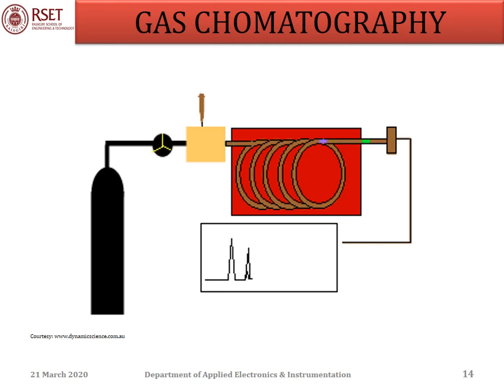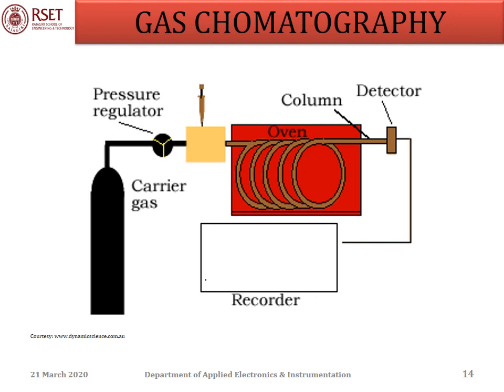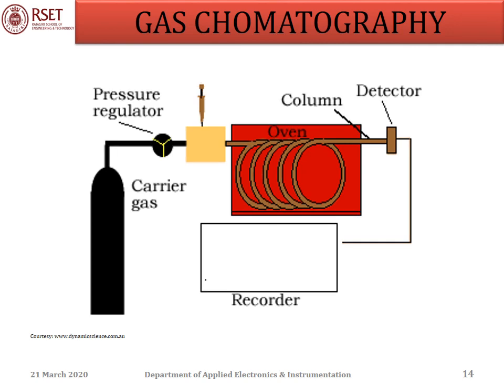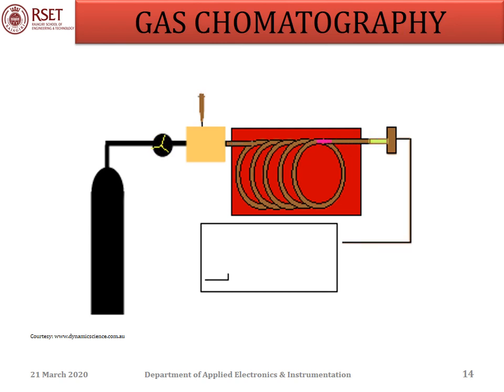Temperature T2 determines the time for passage of the solute and the resolution and efficiency of the column. At the end of the column, a detector is placed which produces an electrical signal corresponding to the quantity of solute leaving the column. The detector signal can be directly applied to a recorder, producing a chromatogram, or the signal can be applied to the microprocessor for further processing.